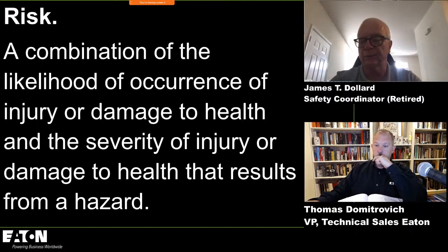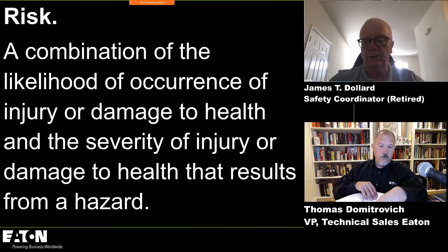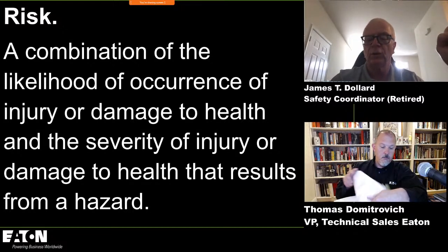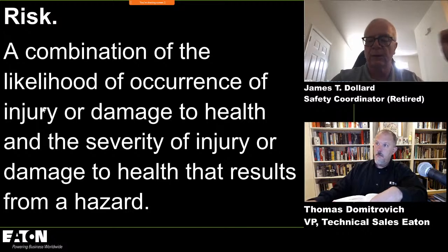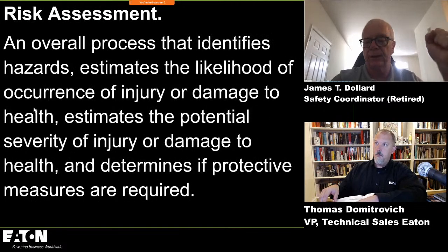The answer is yes, but is it likely? The answer is no. So we always have to take a look at likelihood. And we tell you in the standard, when we get into, for example, table 130.5C in 70E, that likelihood of occurrence is just one piece of a risk assessment. You must always look at the severity of injury or damage to health.